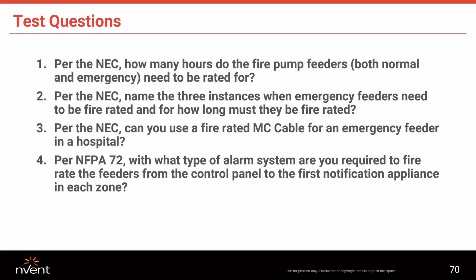The first question, per the NEC, how many hours do the fire pump feeders, both normal and emergency, need to be rated for? Is that 2? Yes, 2, yes. Ready for the second question? Yep. Okay. Second question, per the NEC, name the 3 instances when emergency feeders need to be fire rated and for how long must they be fire rated?